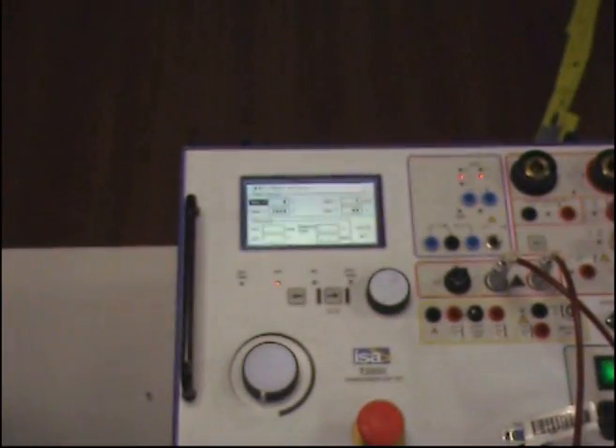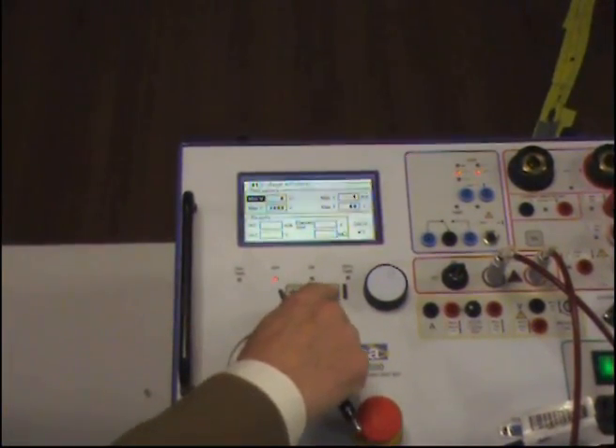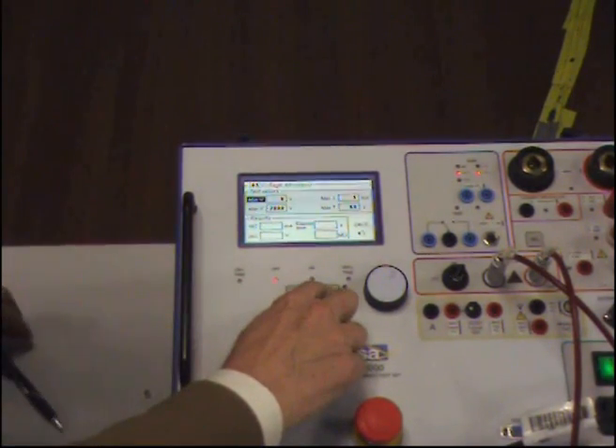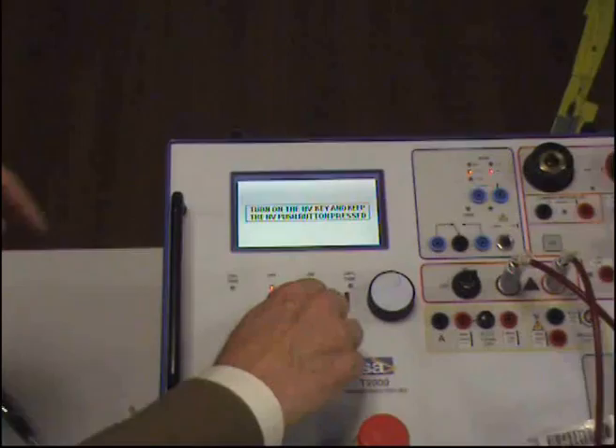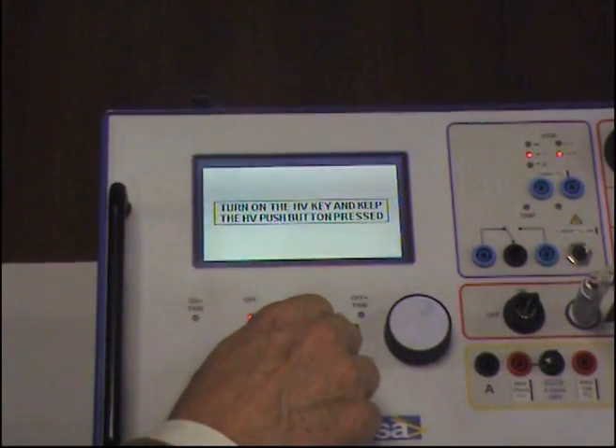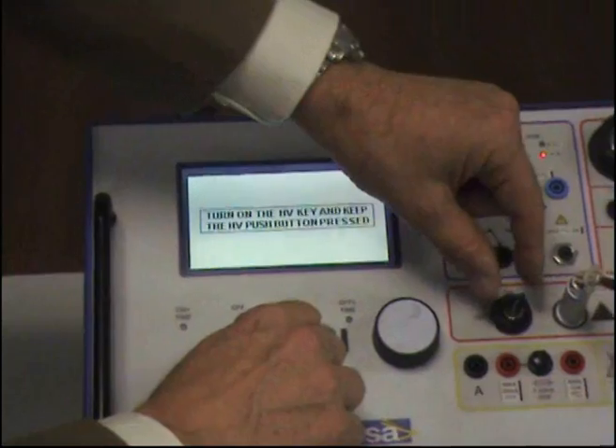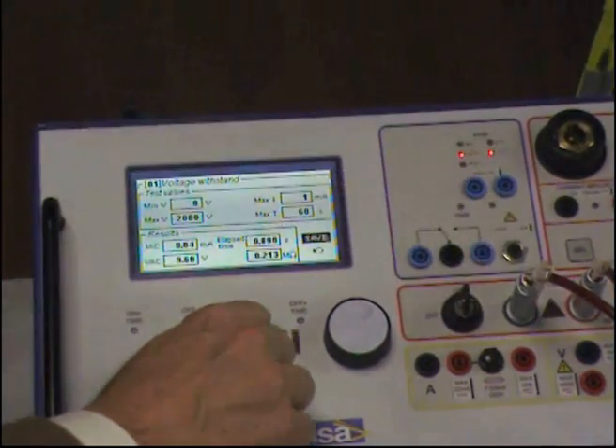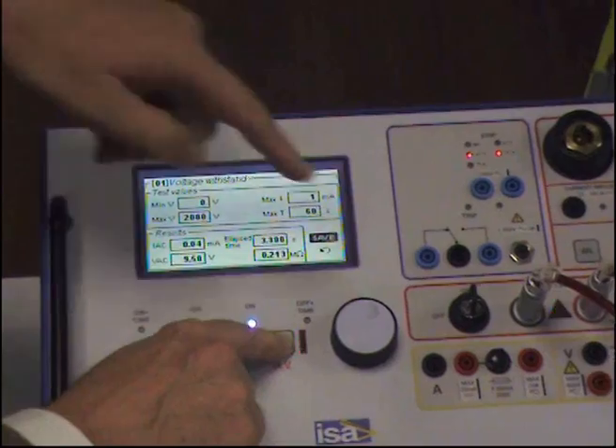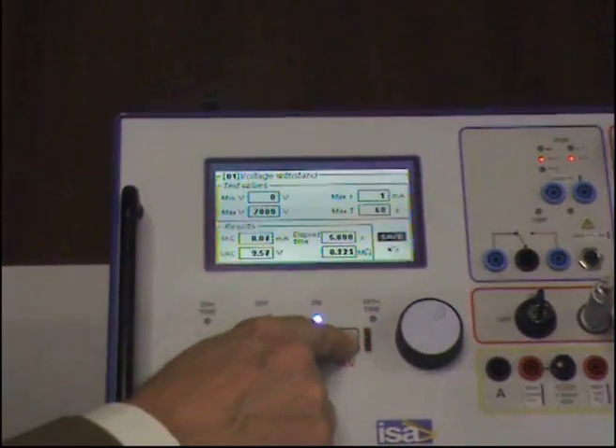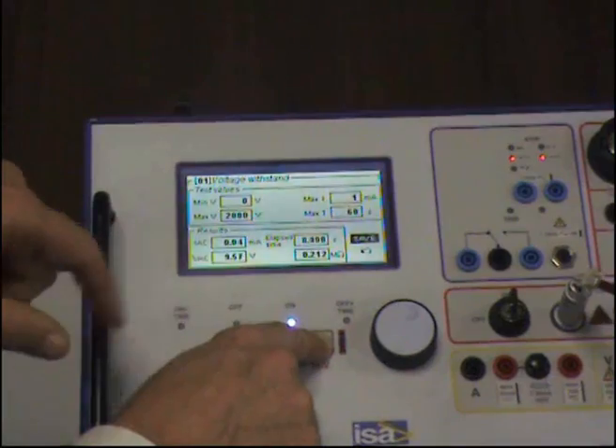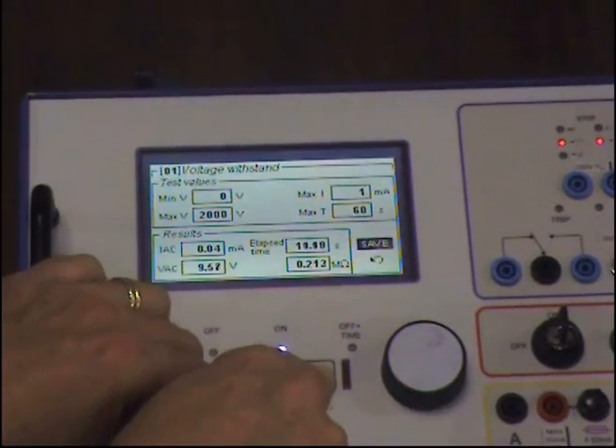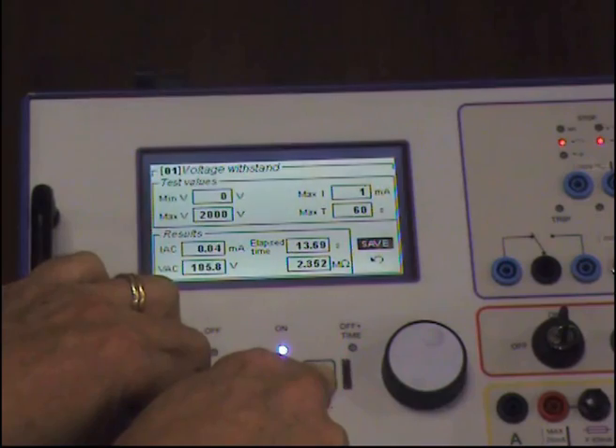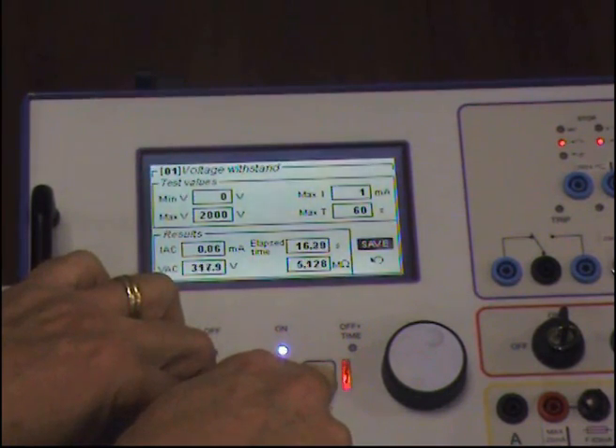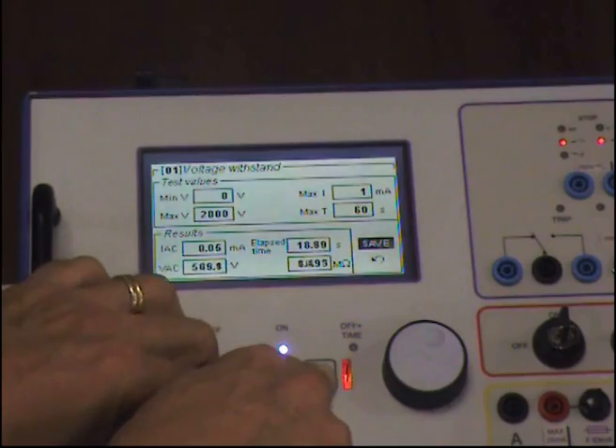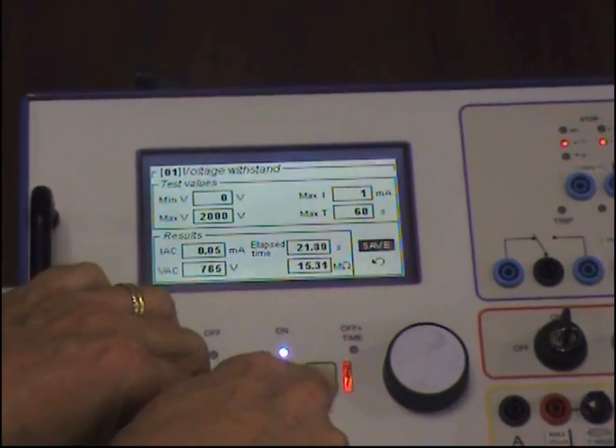So now, if I don't have to change anything, I can just press on. As soon as I do, I have a message: turn on the high voltage key and keep the button pressed. Do you see the key? This is the key. As soon as I turn it on, the lights are flashing, and I do have some voltage applied, very small of course. Now I can raise the voltage to the value that I want. For instance, for this test I go to 1000 volts.